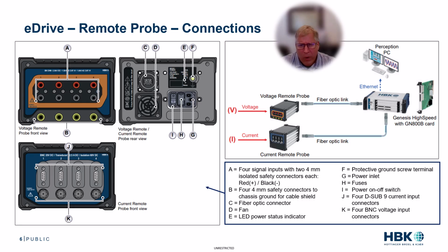Now, one thing to keep in mind is that in order to perform power measurements with the highest possible accuracy, a factory power verification is performed using a specific pair of voltage and current remote probes. Therefore, specific remote probes become each other's companions based on their serial numbers and together form a power channel. Therefore, it's important to avoid swapping remote probes to achieve the highest possible accuracy, and if you'd like further details, you want to be sure and review the user manual.